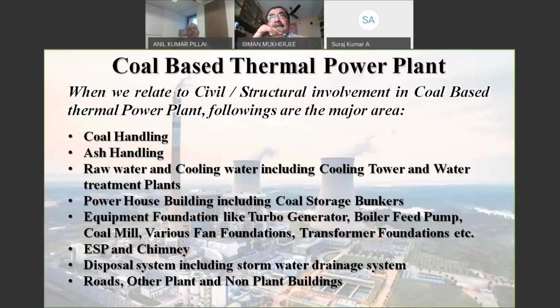with water it is transported to a pit which is called the ash slurry pit. So it is taken to the ash slurry pit, where there are ash slurry pumps, which actually pump the water at a minimum ratio of 10 to 1, 10 parts of water to 1 part of ash, and that transports this ash to the ash pond, the disposal pond.